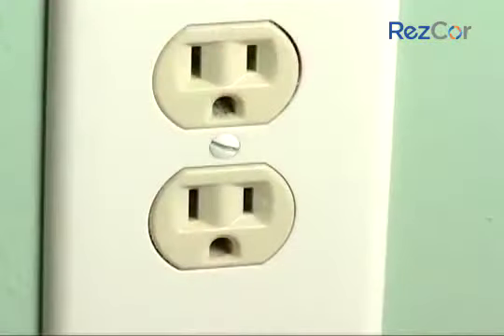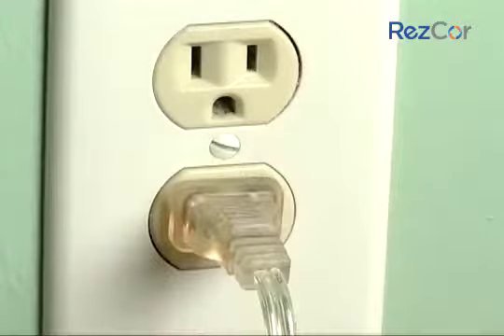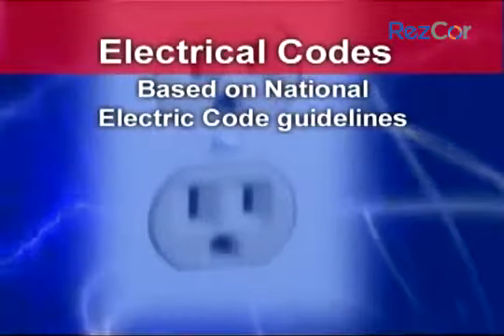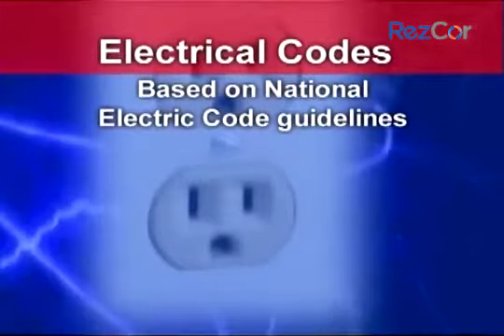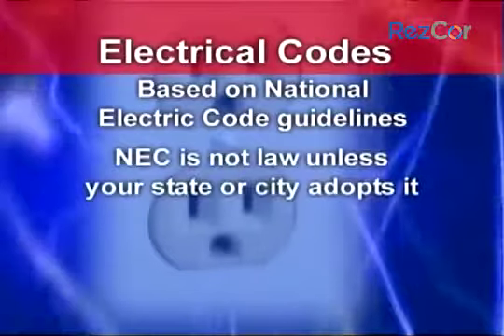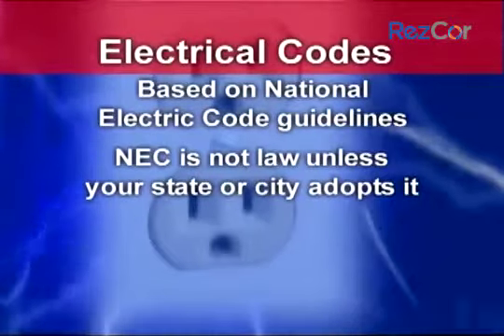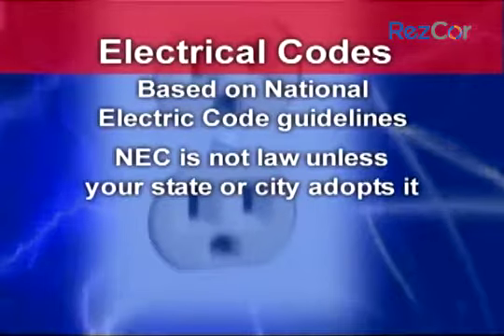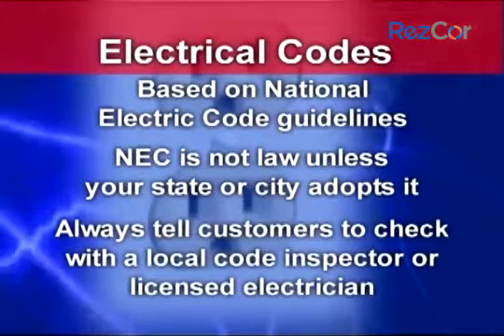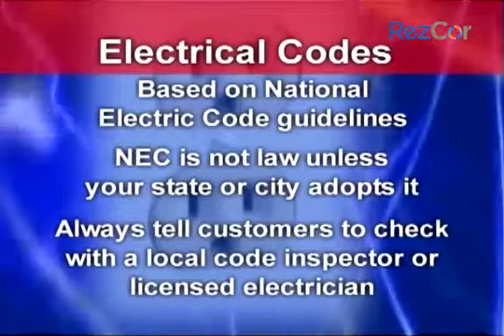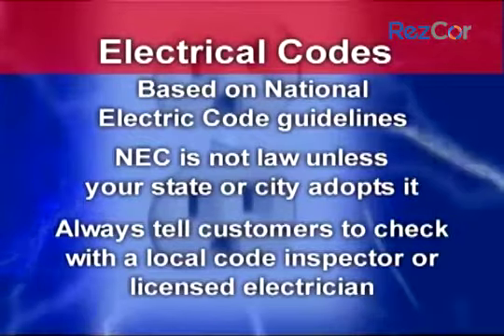After your circuits leave the main panel, they run through your house and provide power to receptacles, lights, appliances, and so on. Each cable that is used to connect to these devices is sized according to your local codes. These codes are based on the National Electric Code guidelines. The National Electric Code is also known as the NEC, and it's not law unless your state, city, or town adopts it. For this reason, you should always tell your customers to check with a local code inspector or licensed electrician for the latest code information.